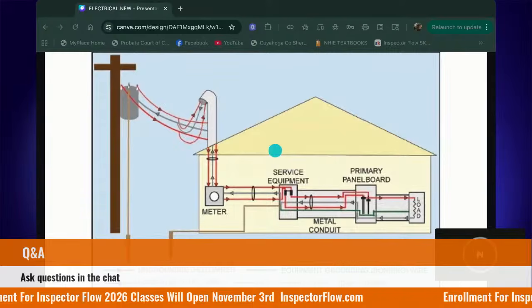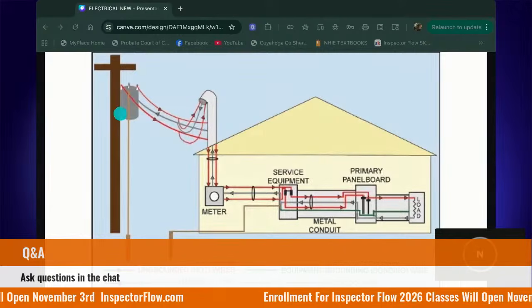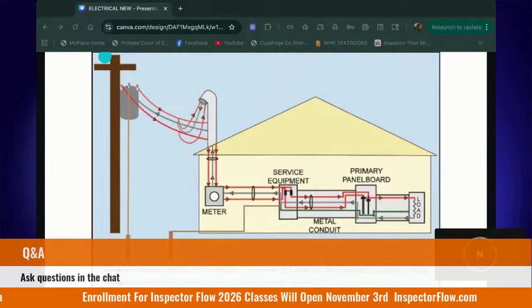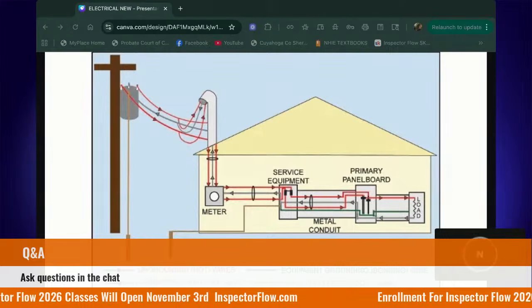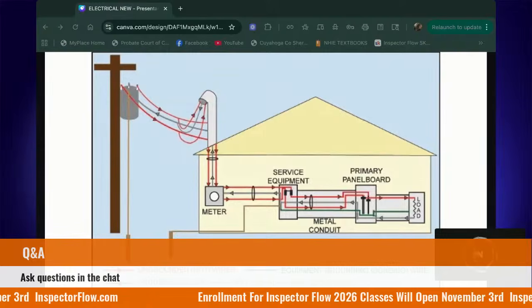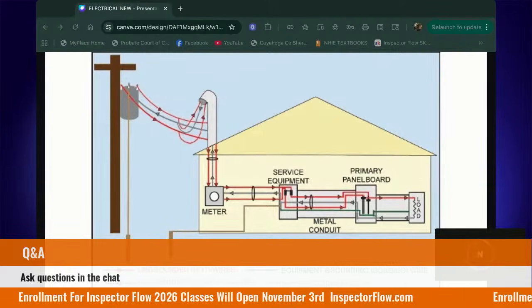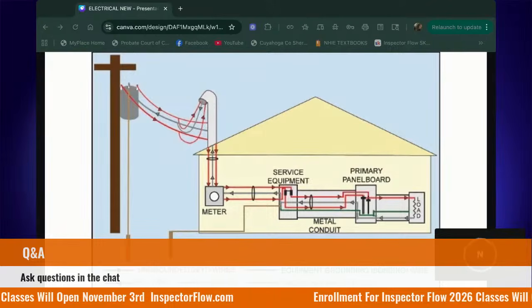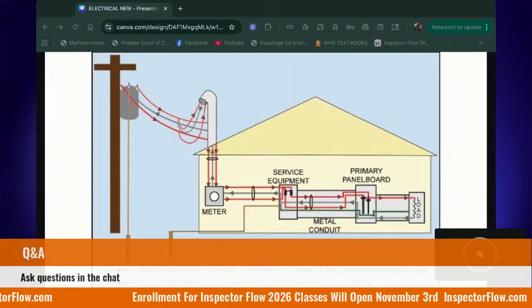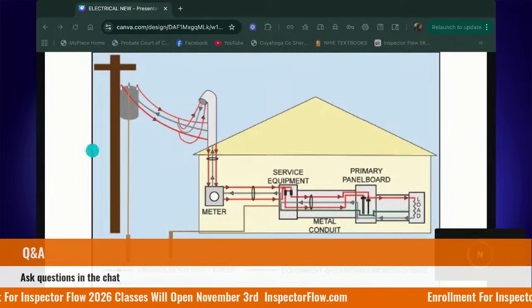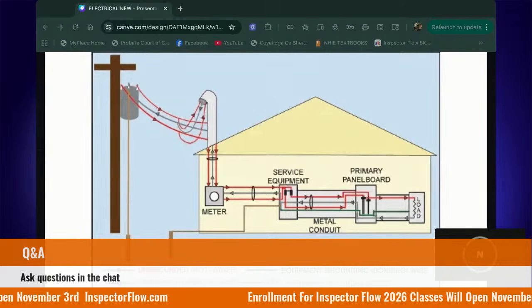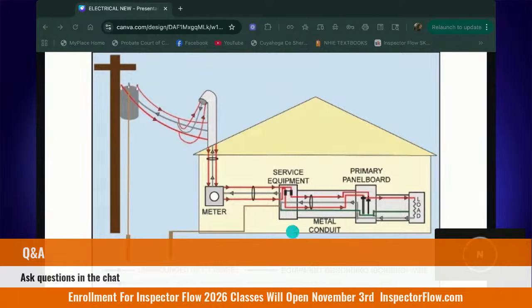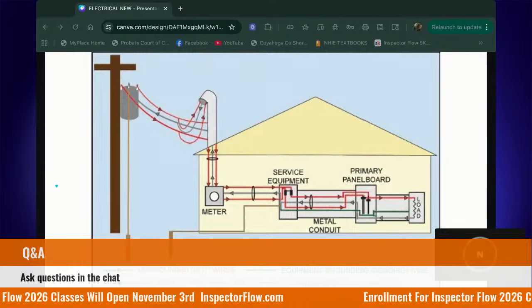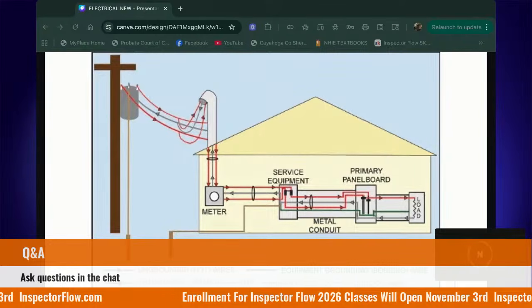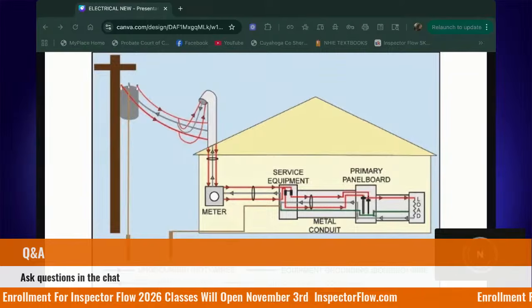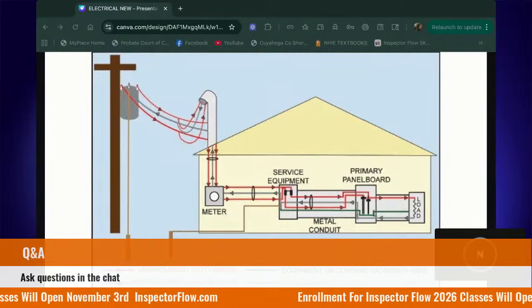So in the case of this diagram, again, we have our power leaving the transformer through our overhead service drop. It travels along our two hot wires and our one neutral wire. The hot wires entering the house each carry 120 volts. Together, they can supply 240 volts for the larger appliances. The electricity passes through the meter so they can count it and charge us. We get to the service equipment. And then in our panel board, we have a GEC. Where would I look to find my GEC?